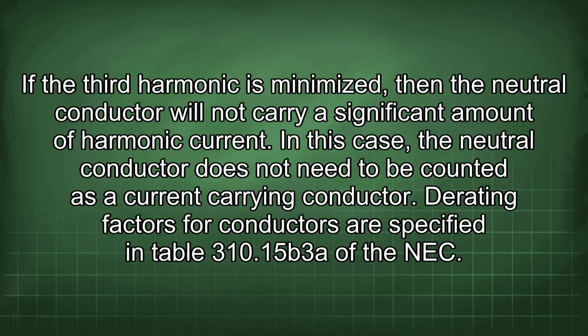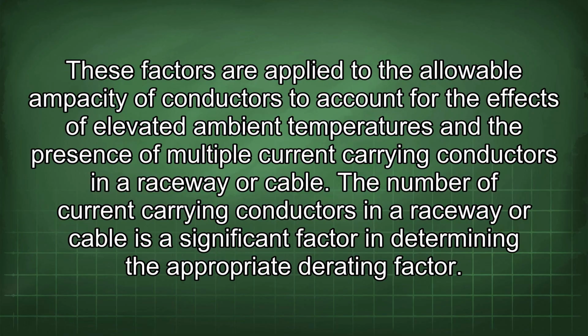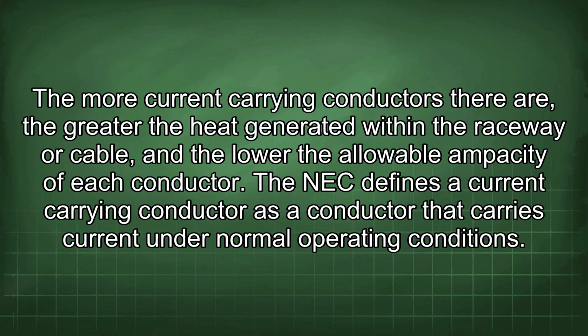Derating factors for conductors are specified in Table 310.15(B)(3)(a) of the NEC. These factors are applied to the allowable ampacity of conductors to account for the effects of elevated ambient temperatures and the presence of multiple current-carrying conductors in a raceway or cable. The number of current-carrying conductors in a raceway or cable is a significant factor in determining the appropriate derating factor. The more current-carrying conductors there are, the greater the heat generated within the raceway or cable, and the lower the allowable ampacity of each conductor.